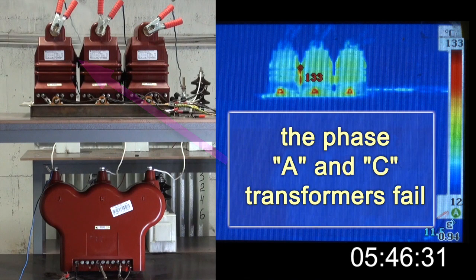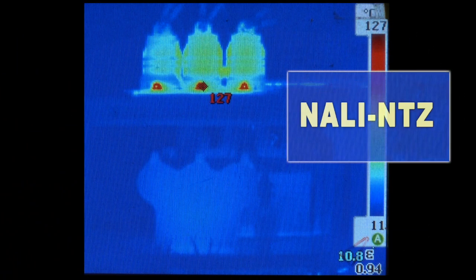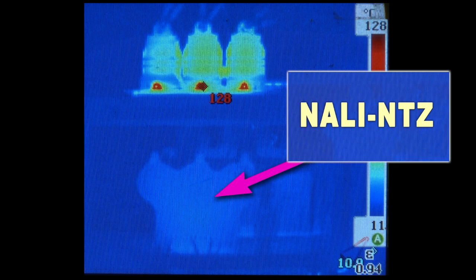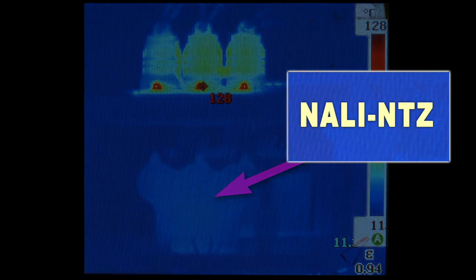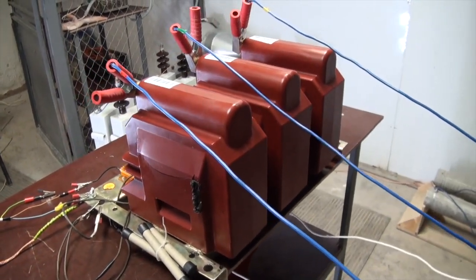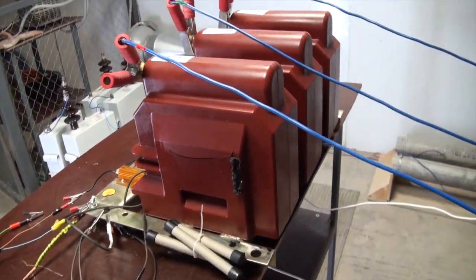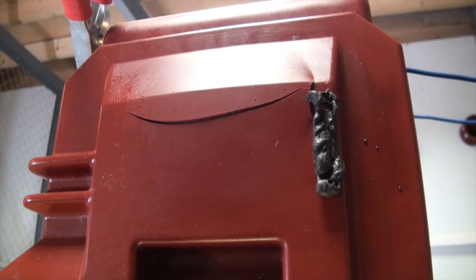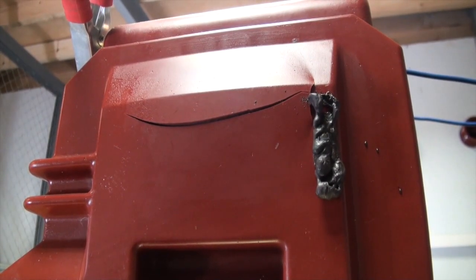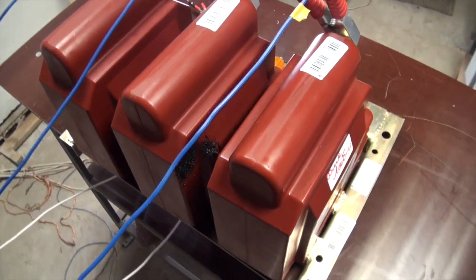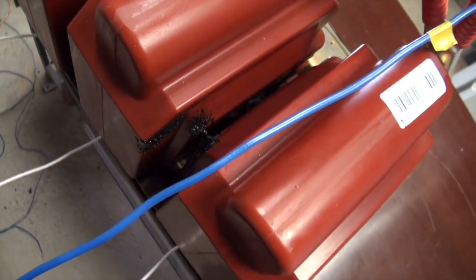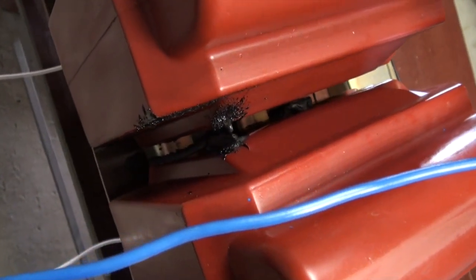At the same time, you can see that the voltage transformer NALI-NTZ easily withstands this mode. It warms up to 25 to 30 degrees and continues to work steadily at this temperature. Under these conditions, the transformer can work indefinitely. As a result of this test, all 3 single-phase voltage transformers and 2 resistors in the neutral of these transformers were damaged. The tests carried out clearly demonstrate the superiority of NALI-NTZ transformers over all other transformers that can control the presence of single-phase earth faults.